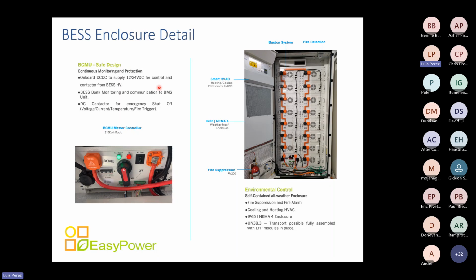Degradation is proportional to battery temperature, but battery temperature is not proportional to your air conditioning temperature. For example, if you take a battery, a hunk of metal with no vents, and put it inside a container, with an air conditioner in the other corner, that's definitely better than not having one, but it's nowhere close to what the battery needs in terms of airflow, because there isn't sufficient natural convection to cool it down during charging and discharging.